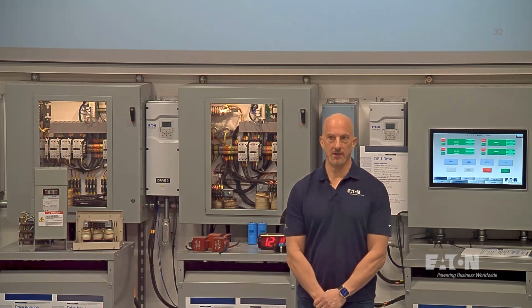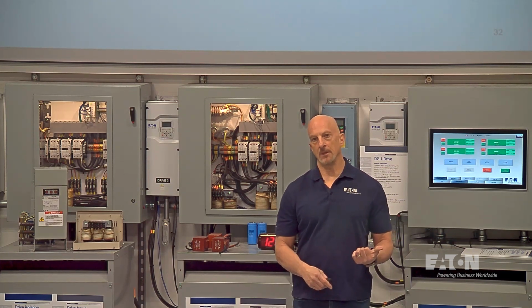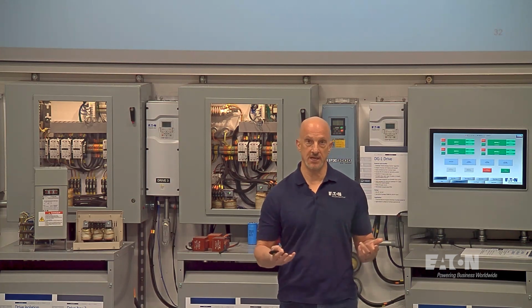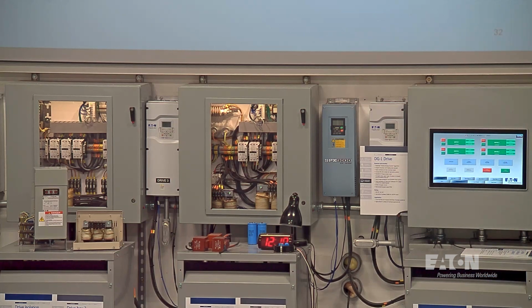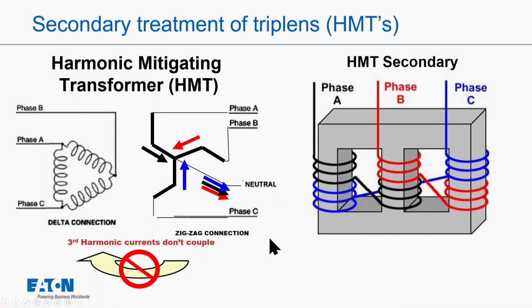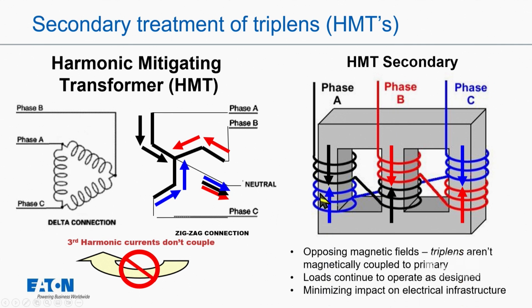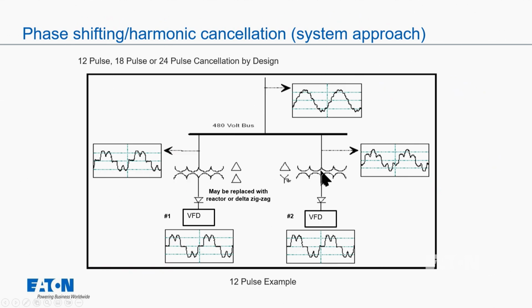And the first way we've talked about in the past is with the phase shifting transformers and the harmonic mitigating zigzag transformers. So let's take a look at that. If we look at a zigzag transformer, we're going to basically not eliminate, but recirculate the third harmonic currents back to the neutral. And the way that works, and we have this in several other videos, is that we actually get cancellation on the leg of the core with, for example, A and C, B and A, and C and B. And then what happens is it doesn't circulate in the delta like a normal delta-Y transformer. But at the end of the day, third harmonics are going back to the load, fifth and seventh are coming through the transformer. So then how do we handle fifth and seventh harmonics?